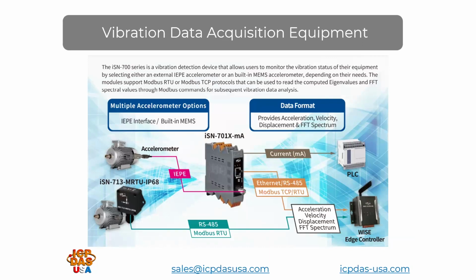The ISN 700 series here is a vibration detection device that allows users to monitor the vibration status of their equipment by selecting either an external IEPE accelerometer or a built-in MEMS accelerometer depending on their needs. The modules support Modbus RTU and Modbus TCP protocols that can be used to read the computed eigenvalues and fast Fourier transform spectral values through Modbus commands for subsequent vibration data analysis.